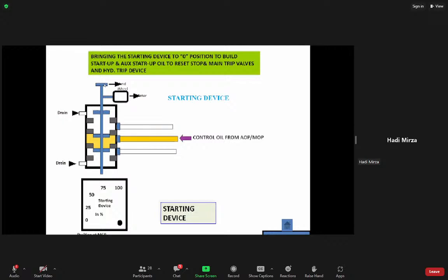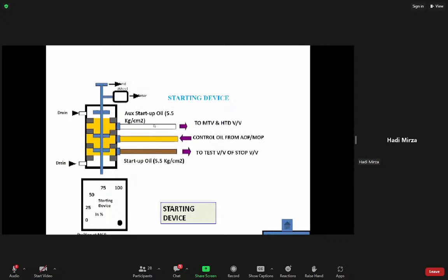I'm playing it once again for proper understanding. This position is from 100 to 0. When you reset the starting device from 100 to 0, the auxiliary startup will generate, and at around 5.5 kg it will go to the MTV, main trip valve, and hydraulic trip devices, that is the overspeed trip release device. And startup oil will go to reset test valves and in turn reset stop valves.